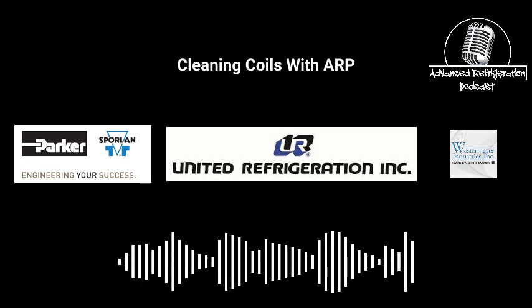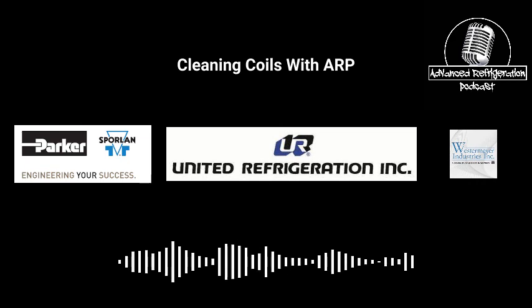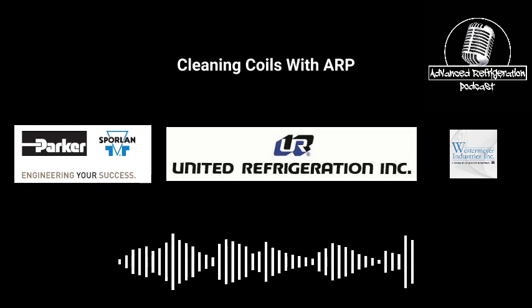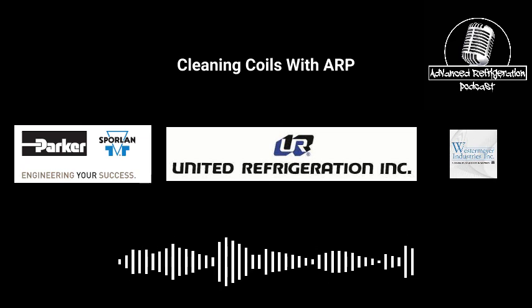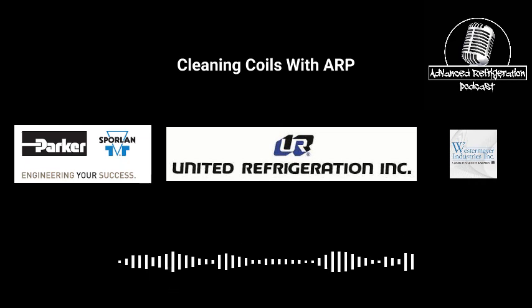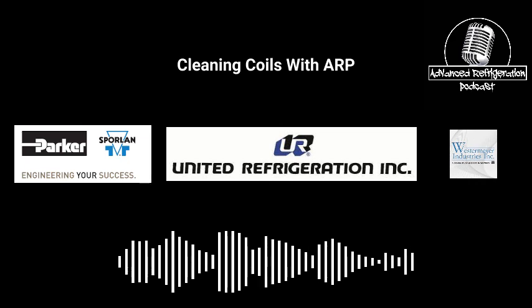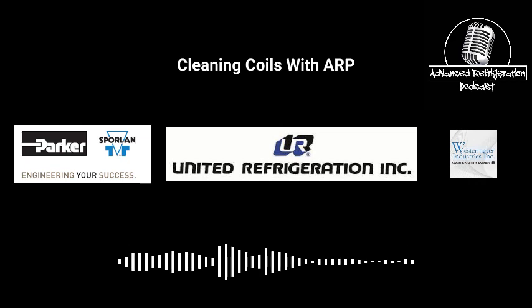We're into spring, starting to hit the heat of summer. So that's where we start having all these issues and where this really starts to matter. I mean, if you guys get ahead of your coil cleaning, it's always better. Up in Chicago, we have cottonwood up here. So generally what happens up here is companies wait until the cottonwood is done flying. It usually takes the first couple 90-degree days to get the cottonwood to fly. And then we have like 2 weeks of hell to get all these coils cleaned, because generally they start popping up on service calls before the apprentices get to them or the power washing companies get to them.